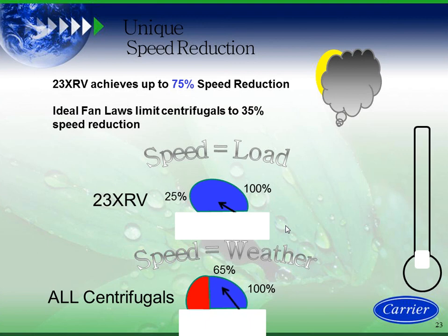One of the key pieces here, and I'm going to go back to the slide again, is that the 23XRV is different than a centrifugal. The reason it's different is because it's a positive displacement machine. It doesn't obey the fan laws that are required on a centrifugal chiller. So I could basically achieve 75% speed reduction on the chiller, whereas a centrifugal can only achieve 35% speed reduction. And a 23XRV is a part load and part lift device.